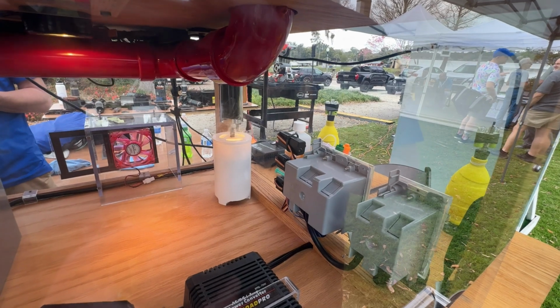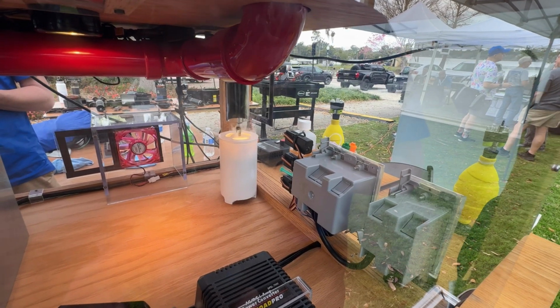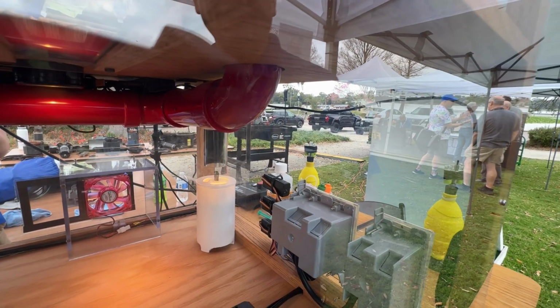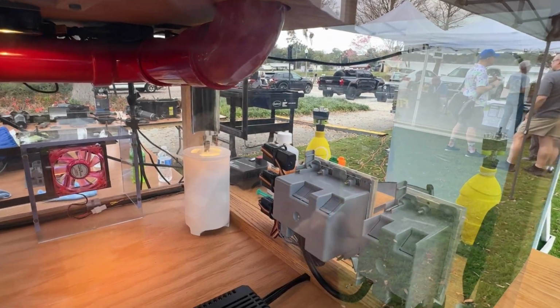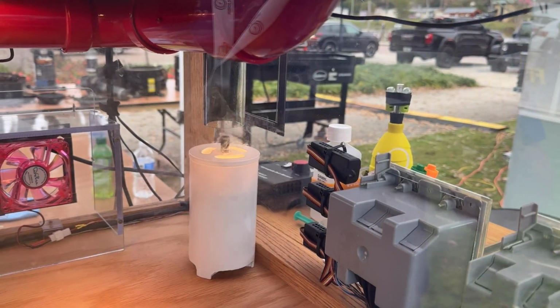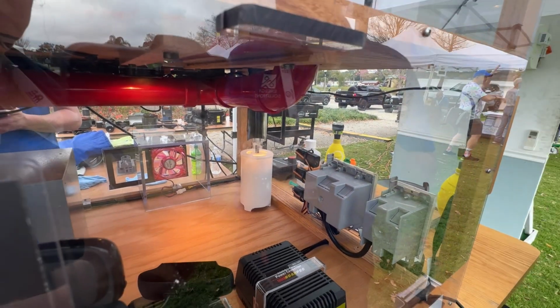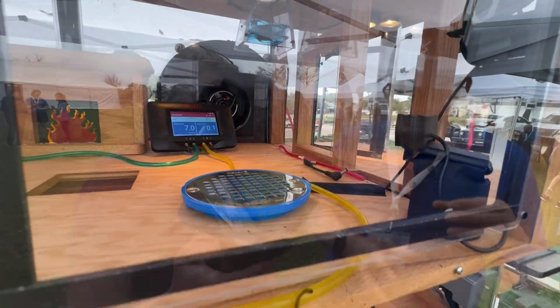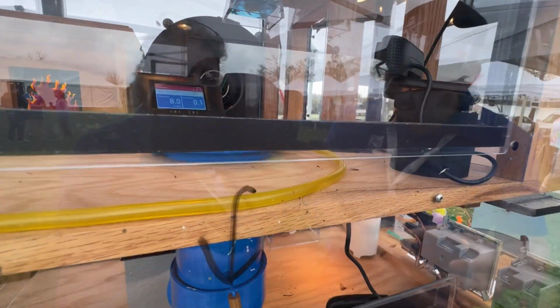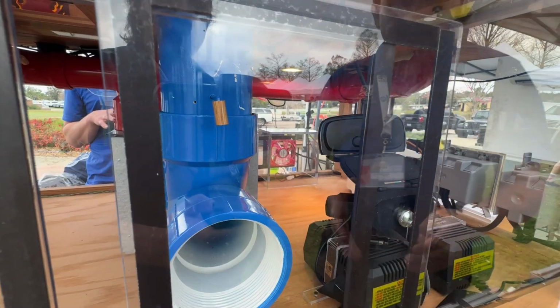And that can kill you. The carbon monoxide is what you're most concerned about. You want the smoke to go up the chimney, but the reason it's not going up the chimney is that the water heater is taking its air to feed the fire from the same space that this return leak is coming from.